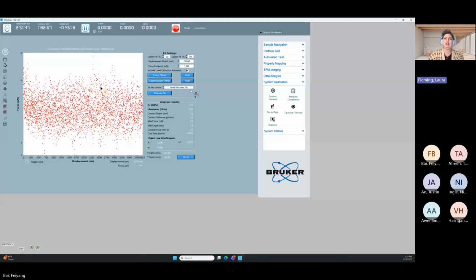So we are in what we call the default workspace. The default workspace saves your sample zones and your methods, so that you can see in this upper right-hand corner. So let's go ahead and make a new workspace for us today for this training. When or after we accept that, that's what we need to do on this page. We don't need to execute the fit. Nope, because we're not testing a material, right? The execute fit button does a power law fit to the unloading curve of an indent, and then you get your reduced modulus and hardness. Here, that's not what we're doing, right? We're doing a calibration. We're just indenting into air. So there is no fit to be had.